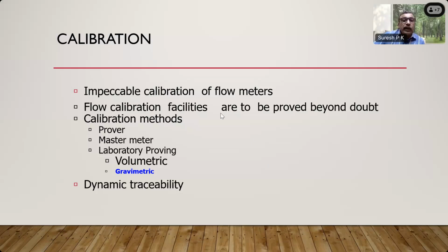The calibration of flow meters can be done by different methods. One is the prover. There are online provers, such as ball provers and different kinds of provers. The fluid passing through the meter is passed through a pipe section whose volume is known, and what is indicated by the prover is compared with what is indicated by the meter. A master meter is a meter which is calibrated against a known system and is assembled in series with the meter under calibration, and the two readings are compared.